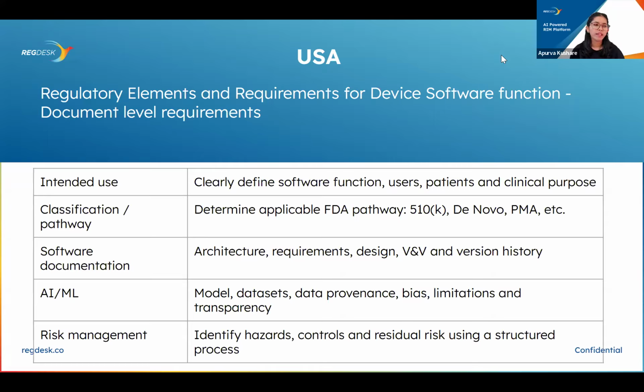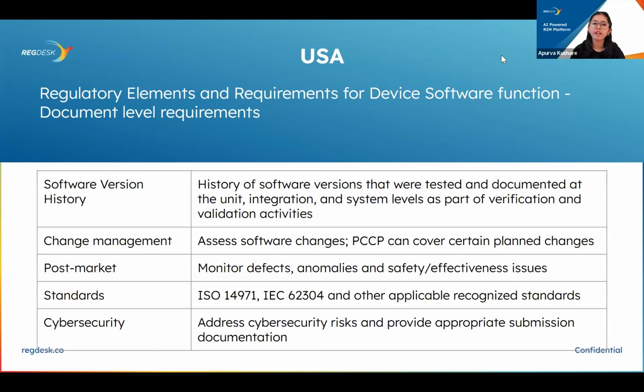Another important aspect is risk management. It should be clear in the risk management plan how the sponsor plans to evaluate the overall residual risk against the benefit of the intended use of the device. It is also important that the manufacturer provides a summary of the processes and procedures in place to manage the software lifecycle development: the software configuration, change management, and software maintenance activities. Moving on to the next slide, we have the software version history. The history of software versions tested and documented at the unit, integration, and system levels are all part of the verification and validation activities.